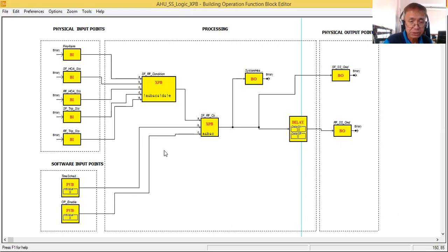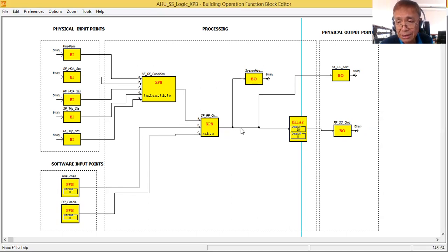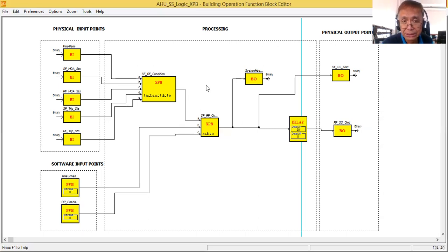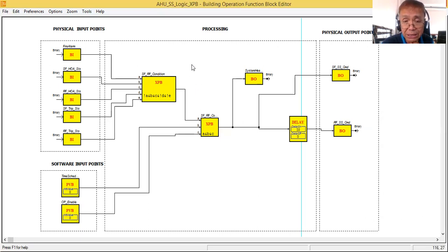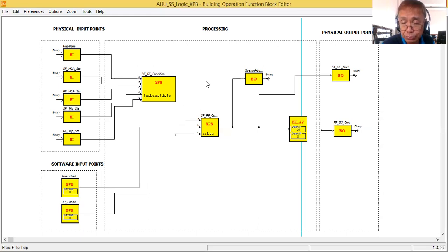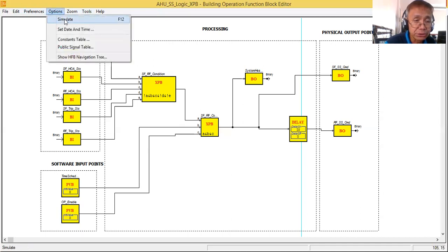I put a time delay on the return fan because I don't want the supply fan and return fan to start at the same time. So this is another approach: instead of using a combination of AND, NOT, and OR gates, you can use an expression block. There are three types: expression block binary, expression block integer, and expression block real.